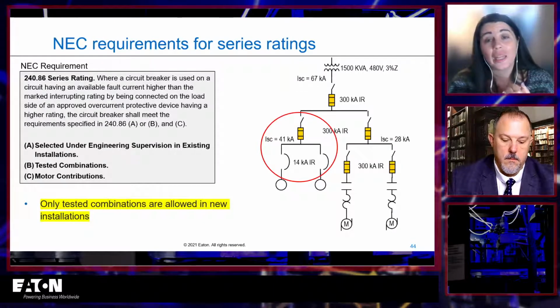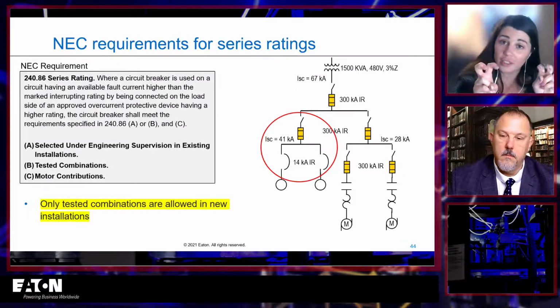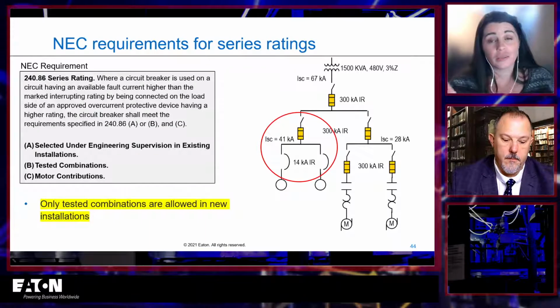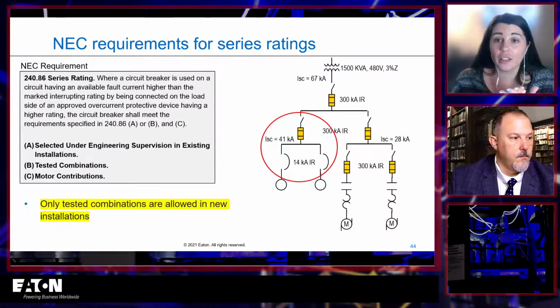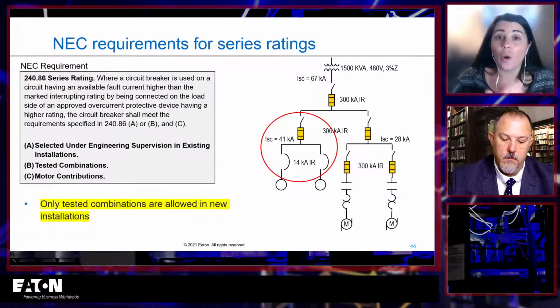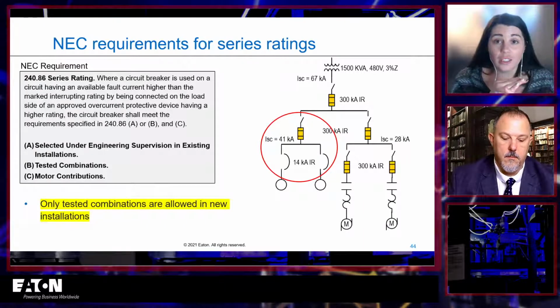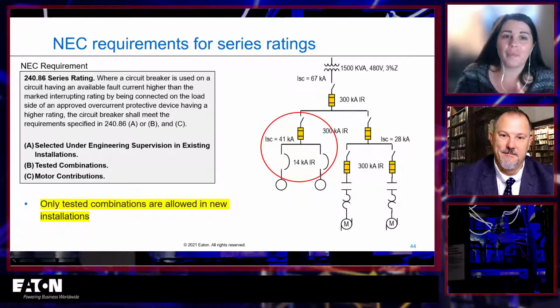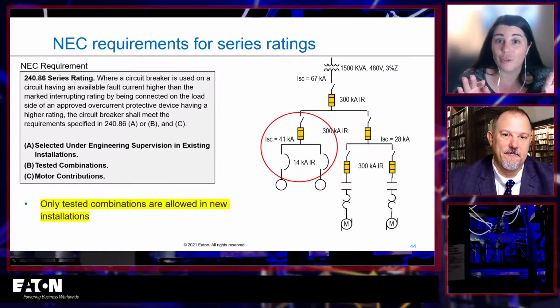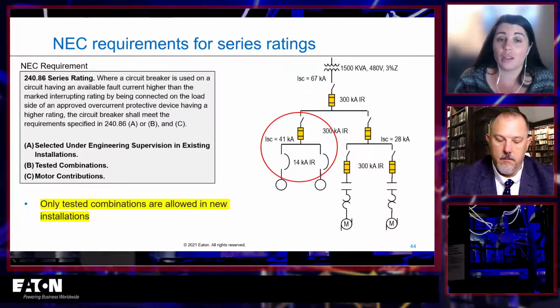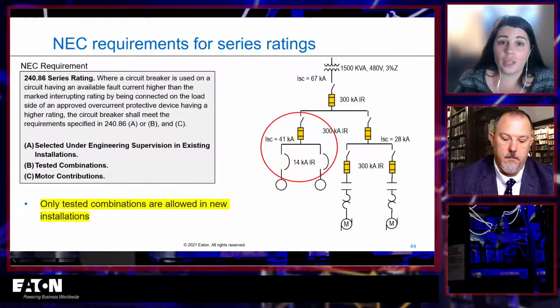The really, really big thing to know is there are engineering solutions to this, and then there are tested series rated combinations. If you are installing a new piece of equipment, you can only use tested combinations. Good news is there are millions of those, but it must be a tested listed combination. An engineering method, which is what most people think of as up over down, which it isn't even necessarily up over down anymore, you can't use that in a new installation. It's only for existing applications that you're allowed to use those. So only use tested combinations for a new one. Go to the next slide.